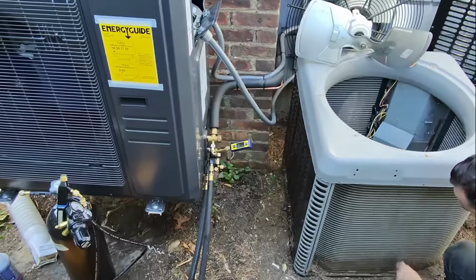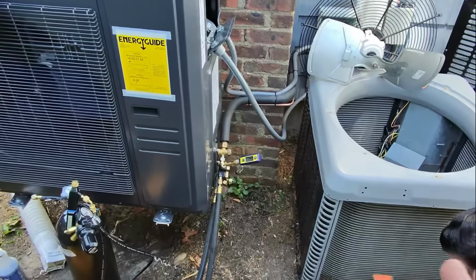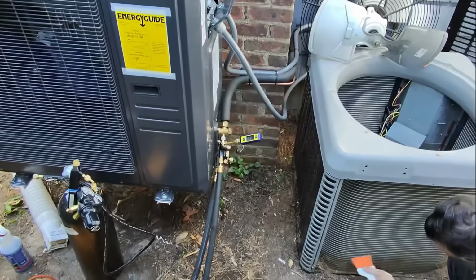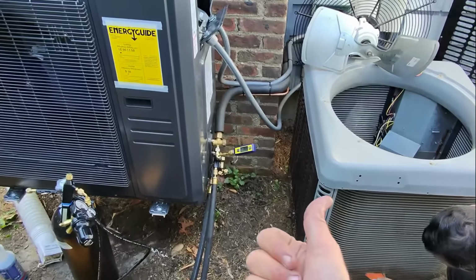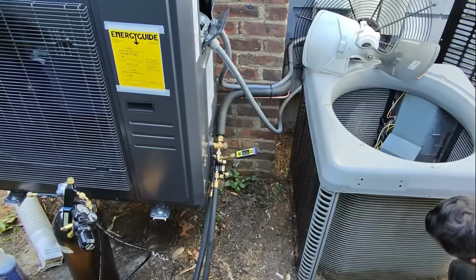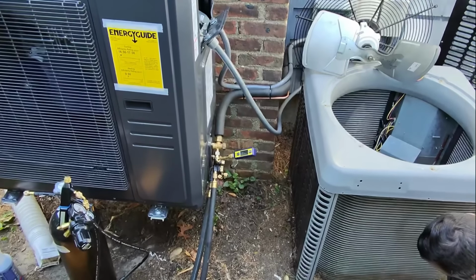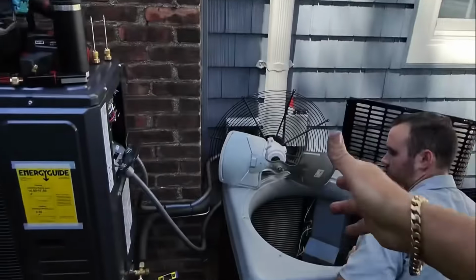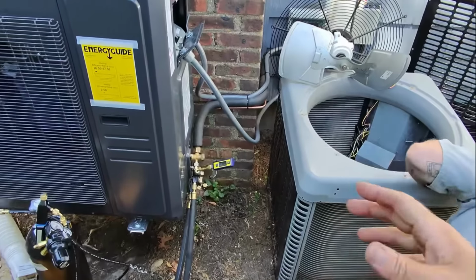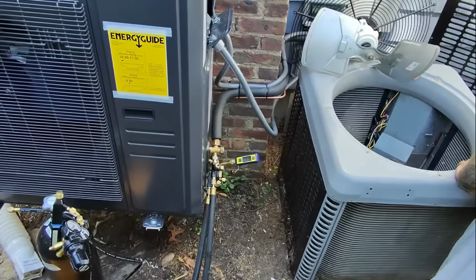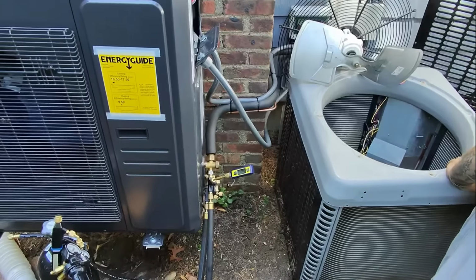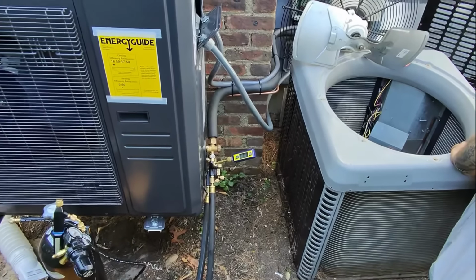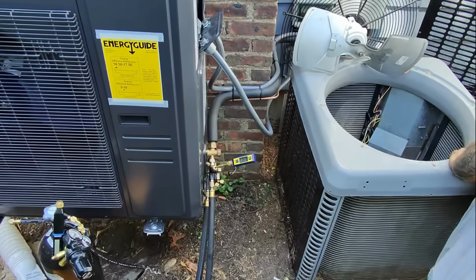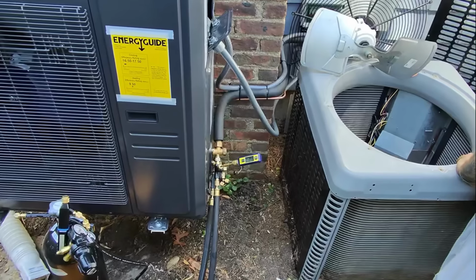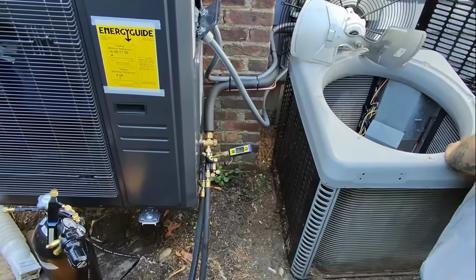So far, so good. This is the most important process of the entire installation. We're removing all the non-condensables and the moisture from the system. Very, very important. Fortunately, we didn't really have any oil to deal with like we sometimes do, where you get an oil trap in the lines, but amazing, that POE oil likes to hold that moisture in it when it's exposed to the atmosphere. Look at it, just went up and went down.